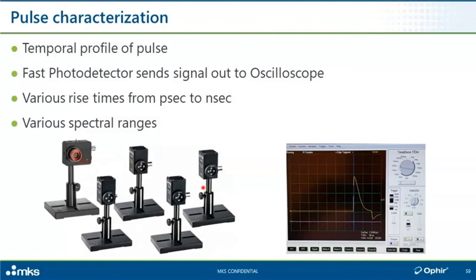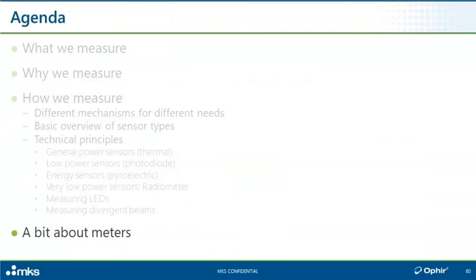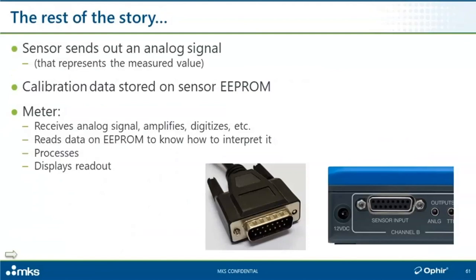Just a couple of words about meters before we conclude. Our standard sensors have their calibration data and other data stored on an EEPROM inside the connector at the end of the sensor cable — we call that the smart connector. Our instruments have a mating D15 connector, and as soon as a meter meets a sensor, it automatically reads all of that data and knows how to work with that sensor — what the calibration factors are, what menus to prompt the user with. The meter receives an analog output from the raw detector element, reads the data, and displays the readout on a handheld display or screen, with some instruments offering direct-to-PC interfaces.